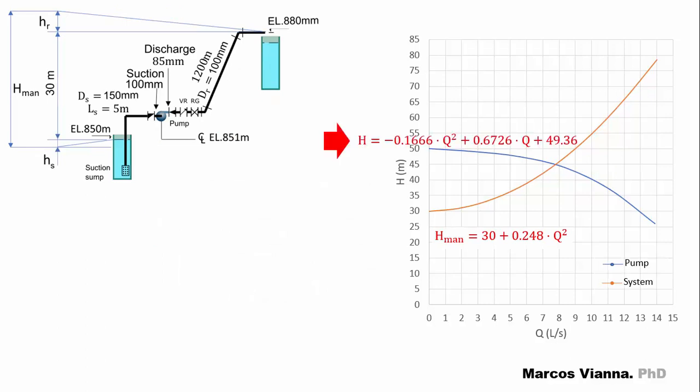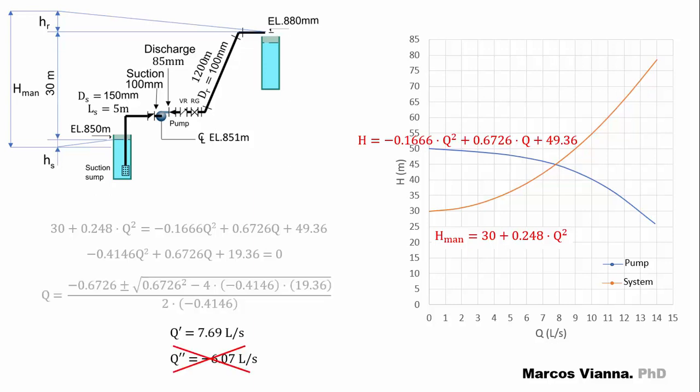But we've also seen that it's easy to find an equation for the system, and if we're able to fit an equation for the pump, we can put together pump and system equations, find a second-degree equation that we can solve, and thus find the crossing points.